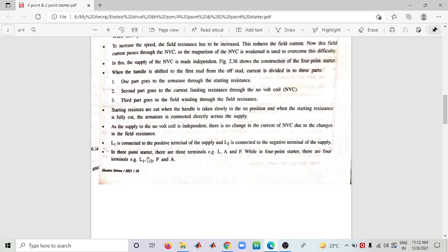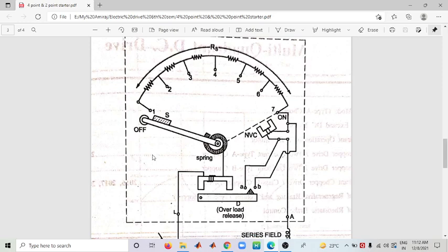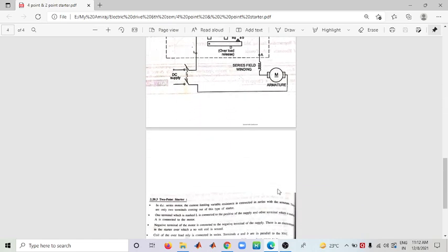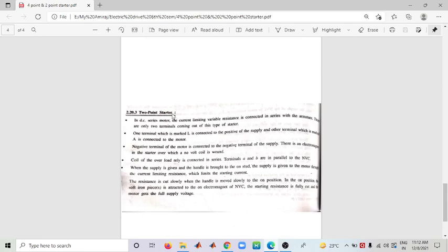Now, the Two Point Starter has only two terminals: L (Line) and A (Armature). Here the series field winding is connected in series with the armature — unlike in the previously discussed configuration where field winding is connected in parallel with the armature. In a Two Point Starter for DC motor, the current limiting variable resistance is connected in series with the armature, and only two terminals come out.